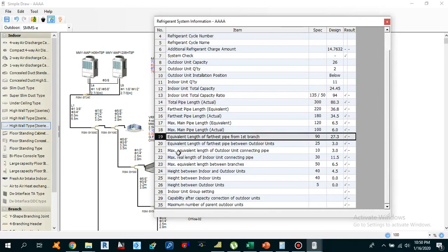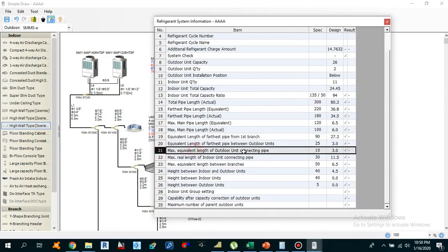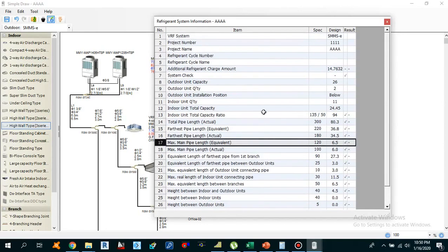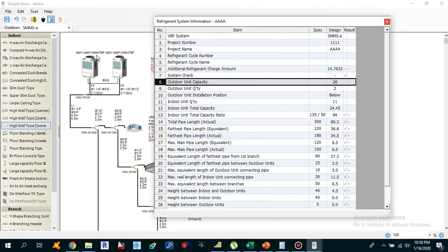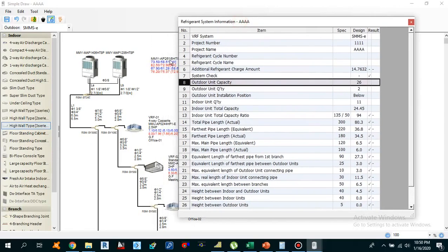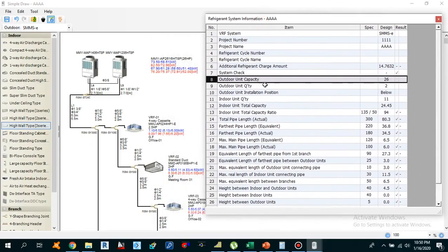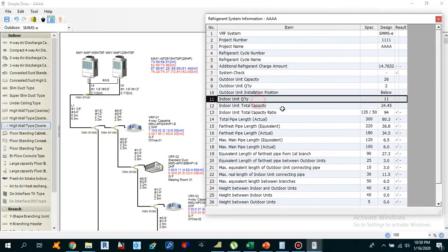Same over here, maximum equivalent length of the outdoor unit connecting pipe is 10 allowed maximum, and we have 3 over here, so we are good. The additional refrigerant charge amount that's automatically calculated for our whole system is 14.76, which is the additional refrigerant amount required to charge.